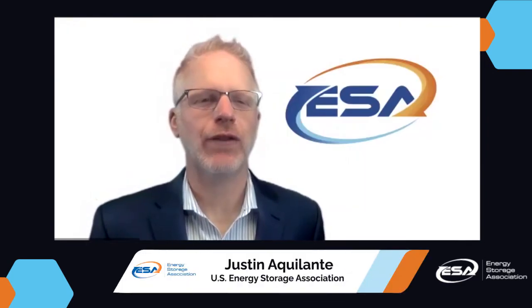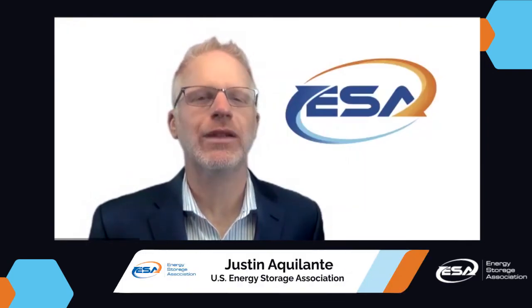Seth, what are the dangers of an undetected electrical ground fault, otherwise known as short to ground? Yeah, that is a very interesting question as well. And it goes back to the answer of the previous question of understanding the difference between a grounded and an ungrounded system. The dangers of an undetected fault will vary depending on which system type you are operating on. So for example, if I'm on a solidly grounded system, then my dangers are immediate. If I have a short to ground, there will be a significant amount of current pushed from my power source, which is generally going to be your battery or your inverter in these types of systems.